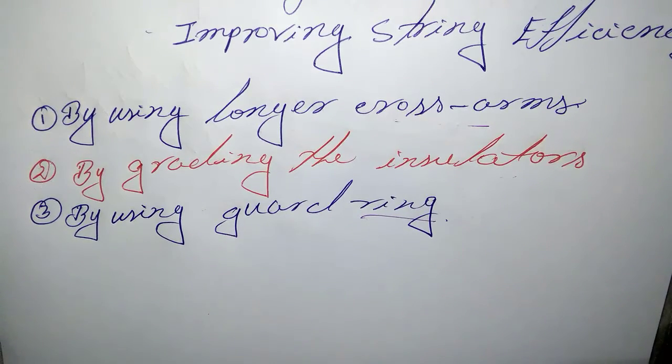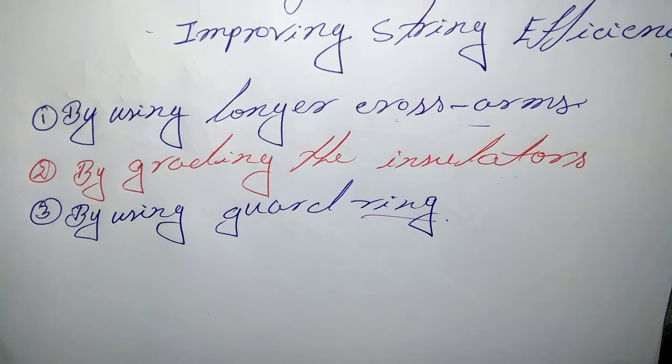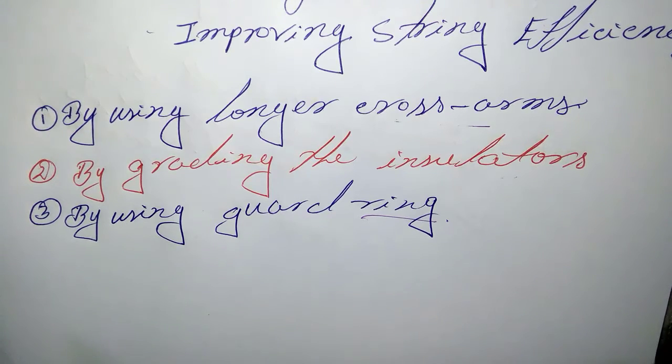Next method is by grading the insulators. In this method, insulators of different dimensions are chosen so that each has different capacitance. The insulators are capacitance graded and assembled in the string in such a way that the top unit has minimum capacitance.